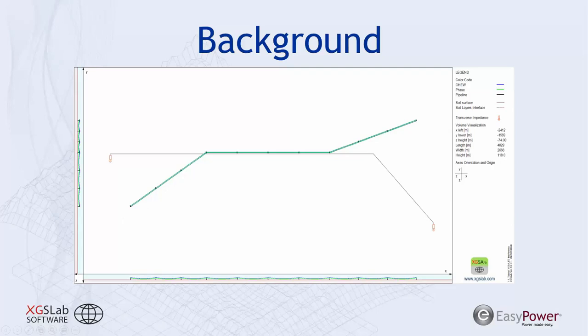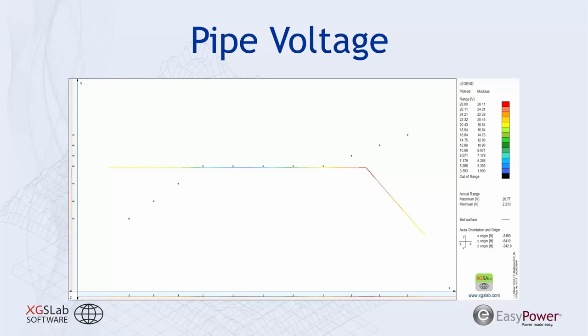So here's kind of our base case. We have approximately 26 or 28 volts as the maximum induced voltage upon the pipeline. And this is a concern, especially if there are any appurtenance in the areas where we have these elevated voltages. And this is a steady state issue, which is going to be present anytime that the transmission line is operating. So when the pipeline personnel are performing their routine tasks like opening valves or checking test leads, they could be subjected to a hazardous voltage at any point.